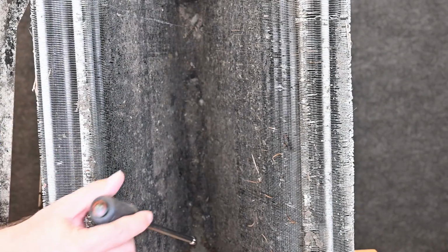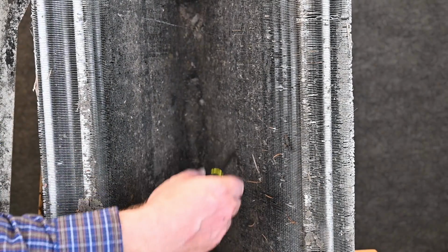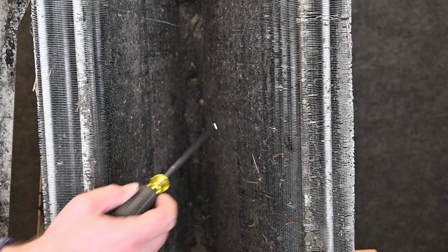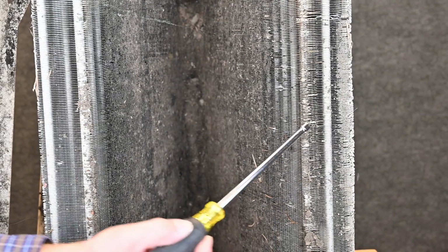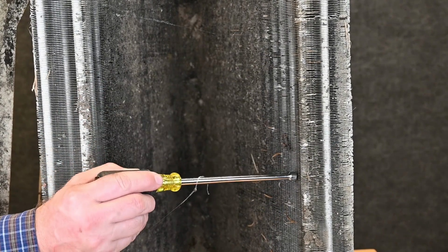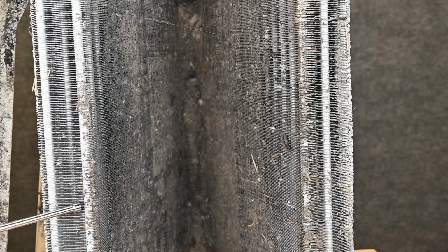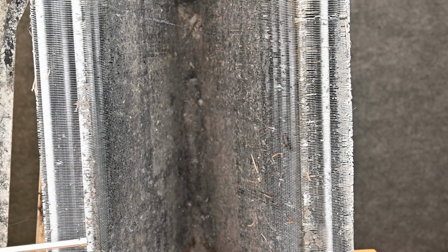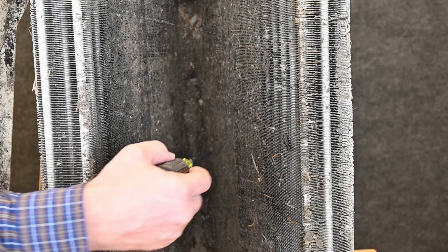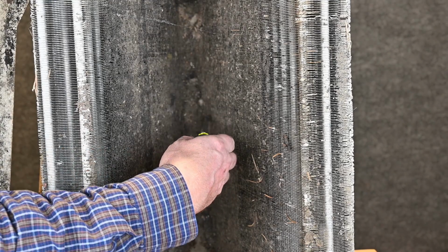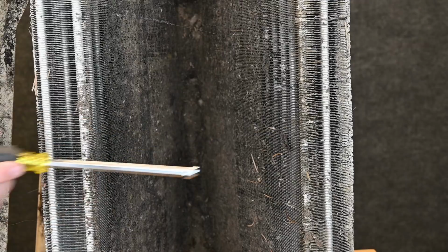here we can see a few things. A lot of people will try to just clean the edge of this evaporator coil, but look at how thick this coil is. See right here on the sides, it looks like it's pretty clean here, but inside you can see that dirt has traveled all the way up inside of this coil. And this is on the bottom side, where there's the least amount of airflow. If we were to take it off at the top, you would see this dirt up here pushed all the way into the inside.